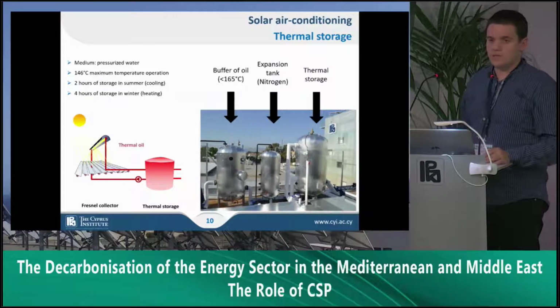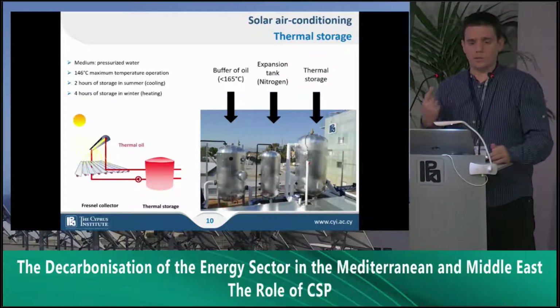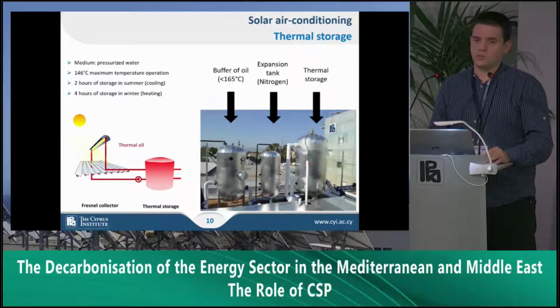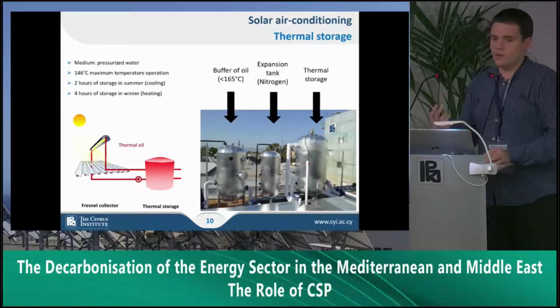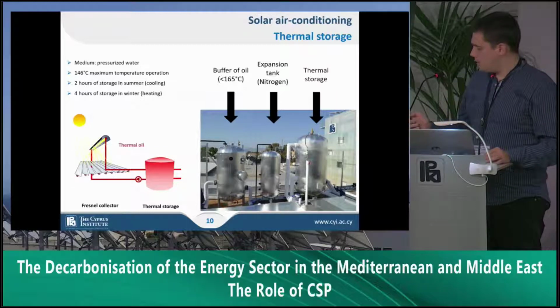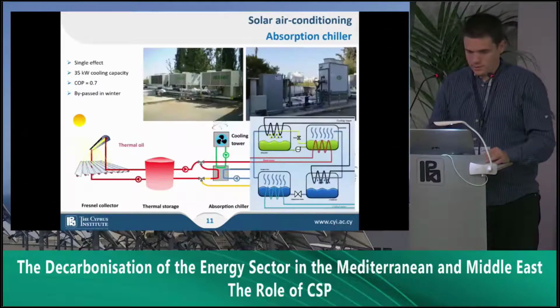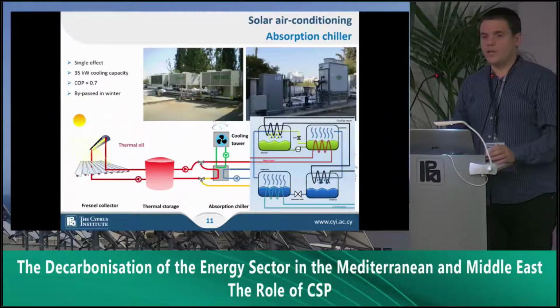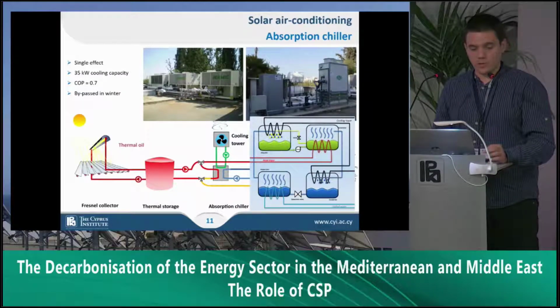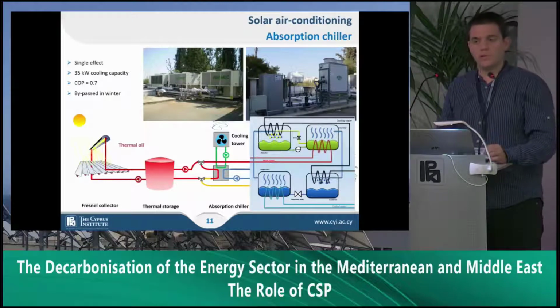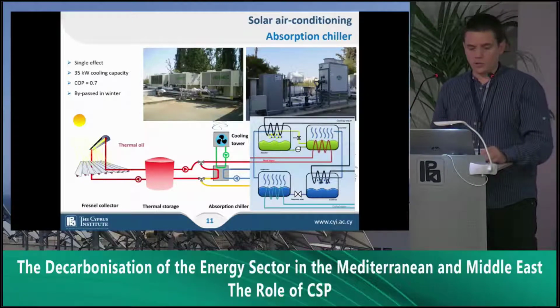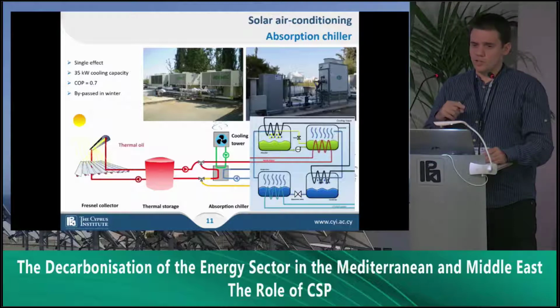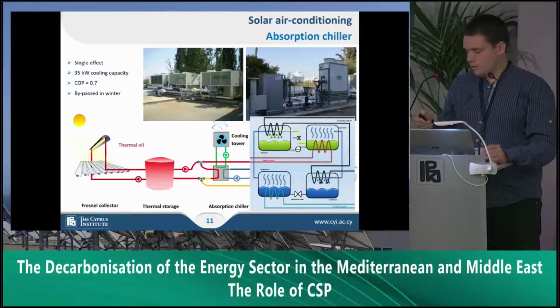This buffer here is simply a buffer of oil with simple heaters wrapped around. So in the morning we avoid the oil being thick for pumping purposes, and this is simply an expansion tank. Cooling is performed with an absorption chiller, single effect, COP of 0.7. It means that it requires 50 kilowatts of heat to remove 35 kilowatts of heat from the chilled water. During the winter, it's simply bypassed, and from the heat of the Fresnel, we go directly to the heating system of this building here.